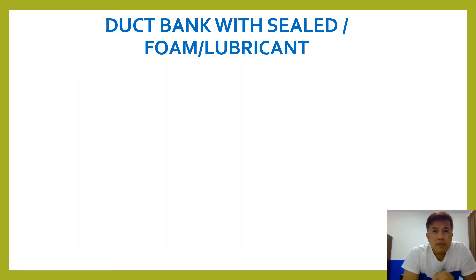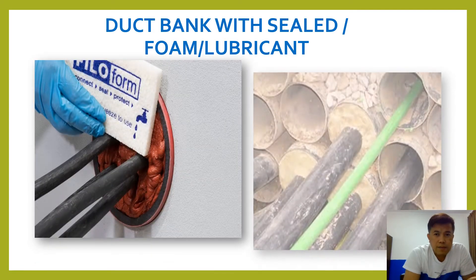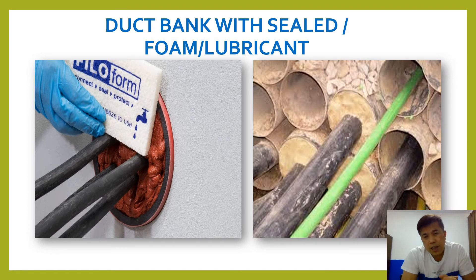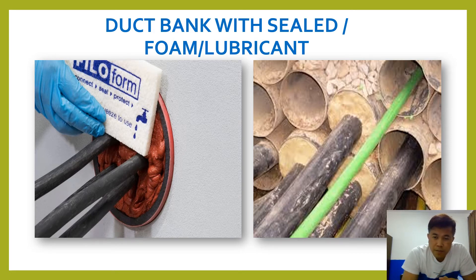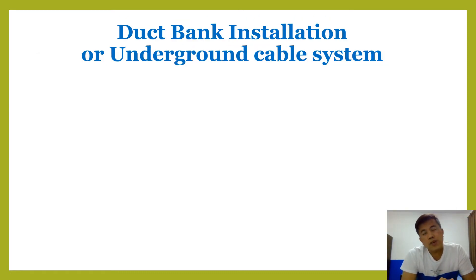Duct bank with seal foam lubricant — as you can see this is one example. On the other side, in the construction side underground, some of the PVC pipe is not covered, not sealed with lubricant or foam — it should be covered. So duct bank is the solution of the underground cable system.